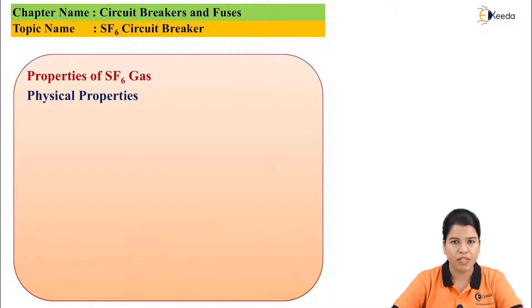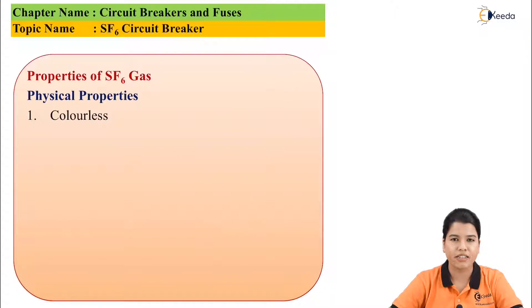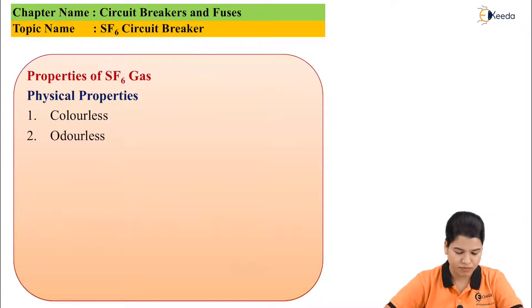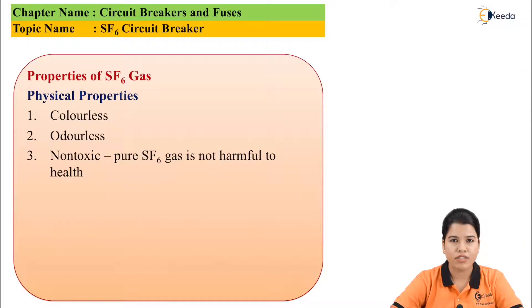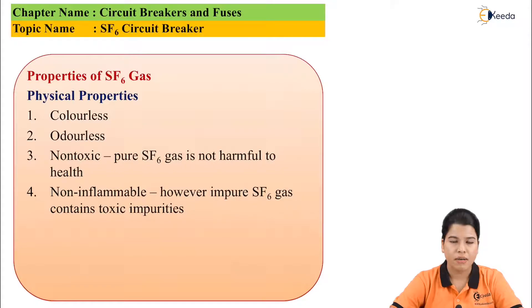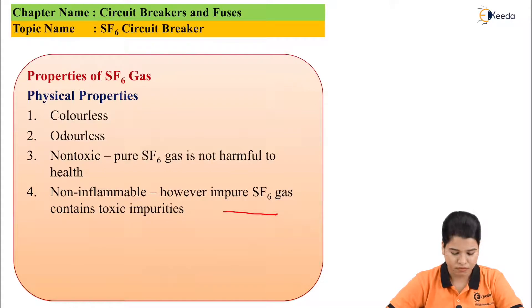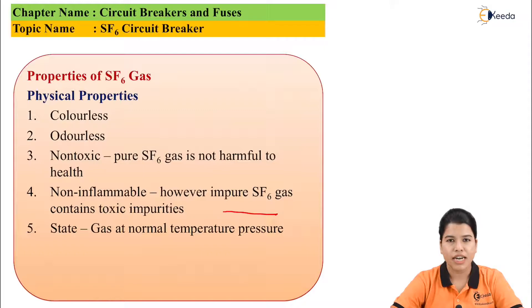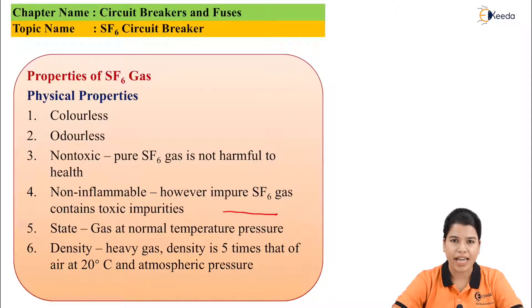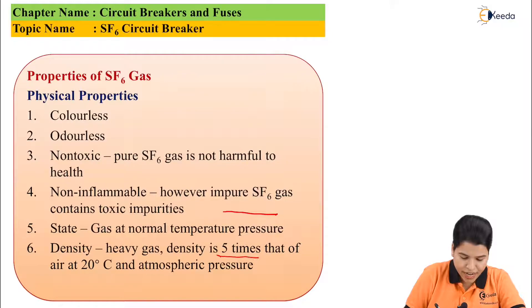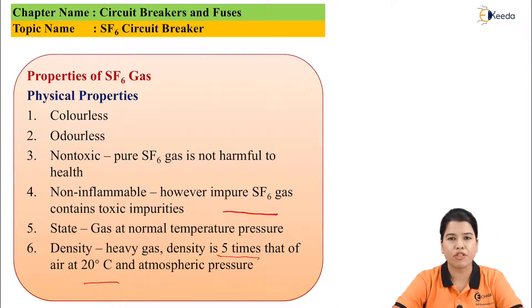Now let us see the physical properties of SF6 gas. First, it is colorless. It is odorless. It is non-toxic — meaning pure SF6 gas is not harmful to health. SF6 gas is non-inflammable, though impure SF6 gas may contain certain toxic elements. The state of SF6 gas is that it is a gas at normal temperature and pressure. Its density is 5 times that of air at 20 degrees centigrade atmospheric temperature.